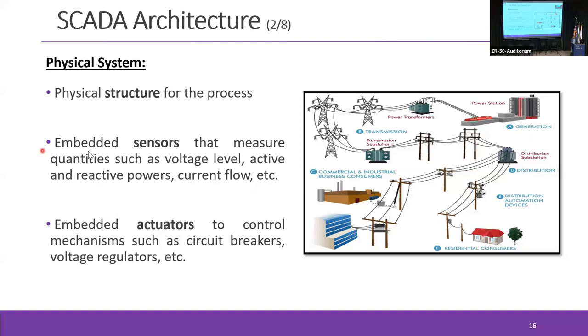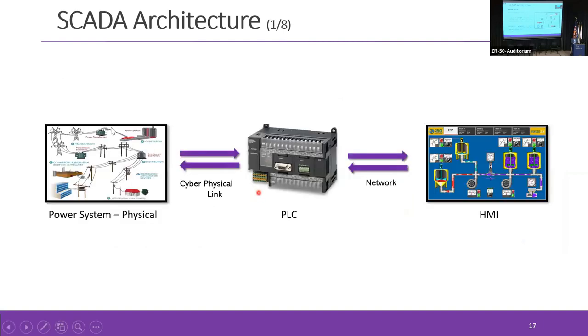Inside this physical system, we have a bunch of sensors. These sensors measure quantities like voltage level, active and reactive powers, current flows, and so on. We also have actuators that control the operation of this system. For example, circuit breakers to connect or disconnect a generation unit or a load from the grid, or voltage regulators to adjust voltage levels, since voltage needs to stay within specific limits. So this is the physical system, the first part of our SCADA system.